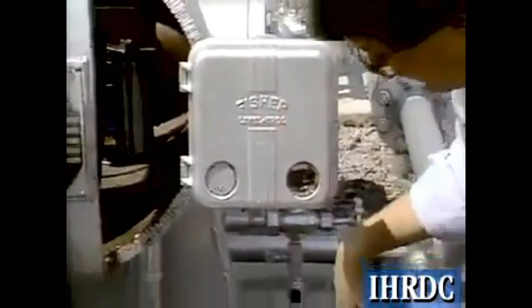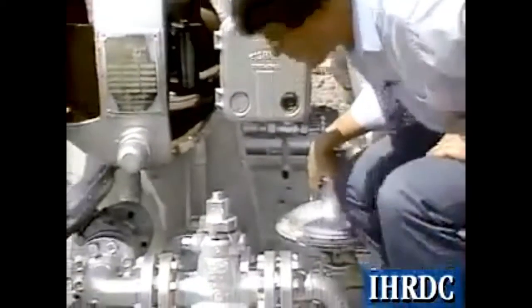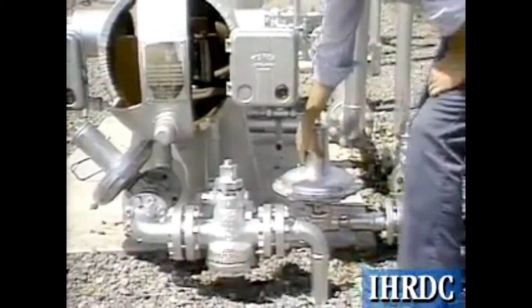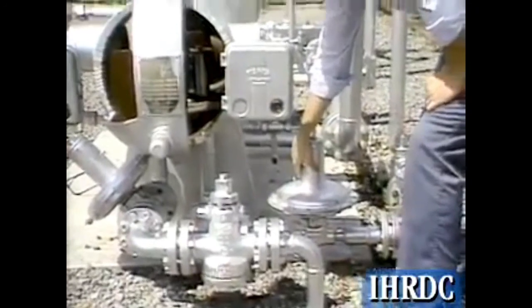Just behind the oil bucket, we see another float which senses the interface between the oil and water within the separator. This float operates another pressure-controlled dump valve down here, which dumps the water from the bottom of the vessel when the interface gets to the certain height it needs to be.